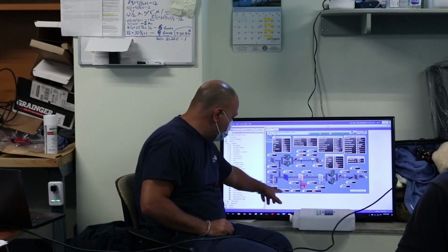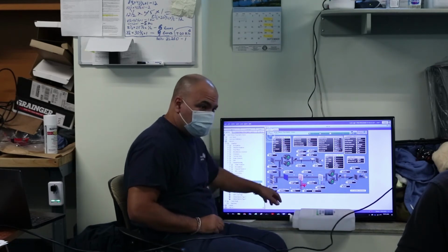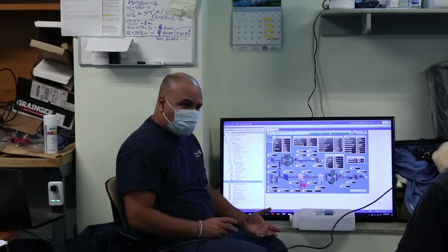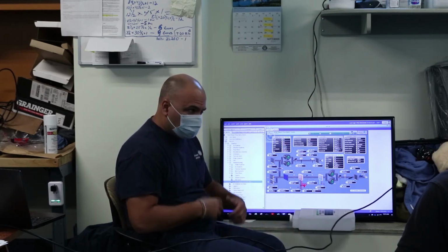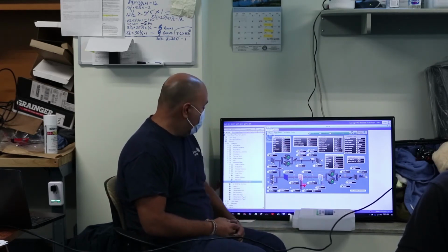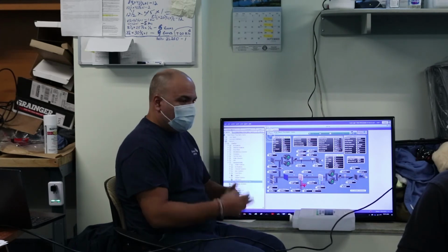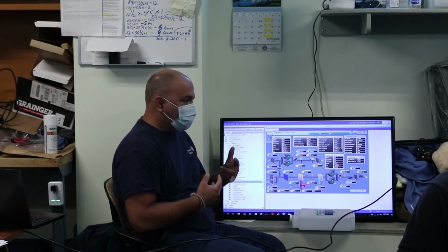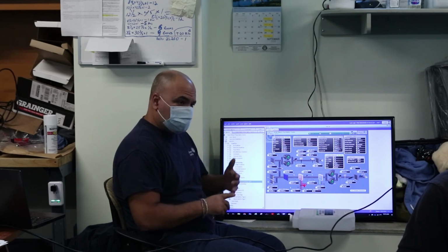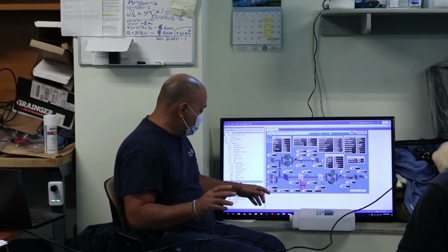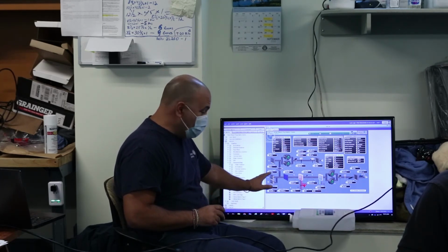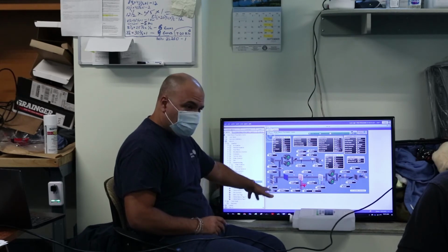So you're going to be looking to maintain 8,500 no matter what mode you're in, other than when the unit first starts up and goes through a recirculation mode. After that, whether you're in heating, cooling, economizer, whatever, you're going to look to maintain that minimum flow first.